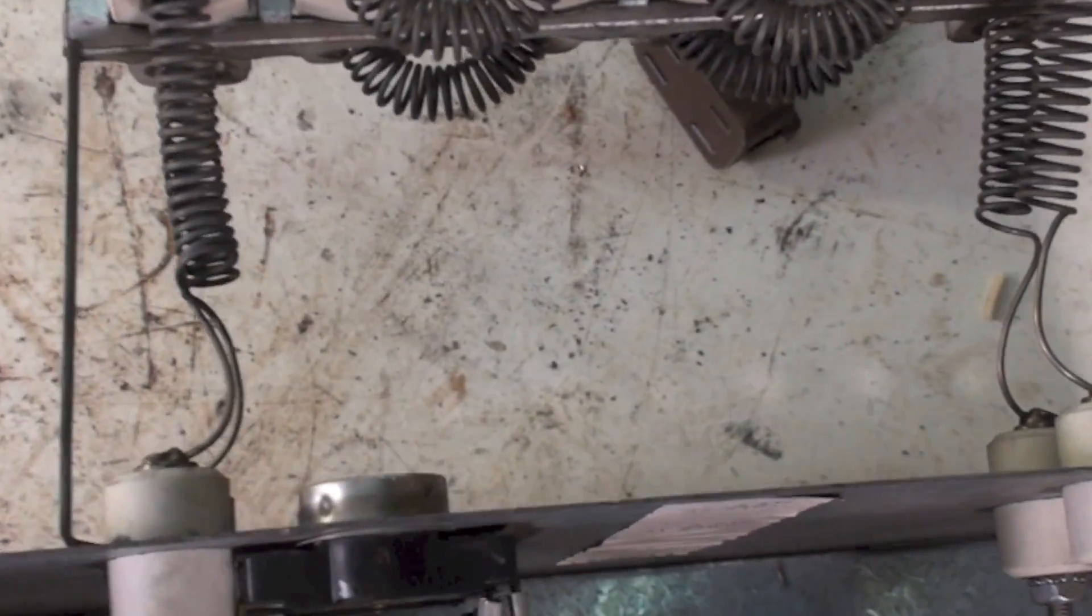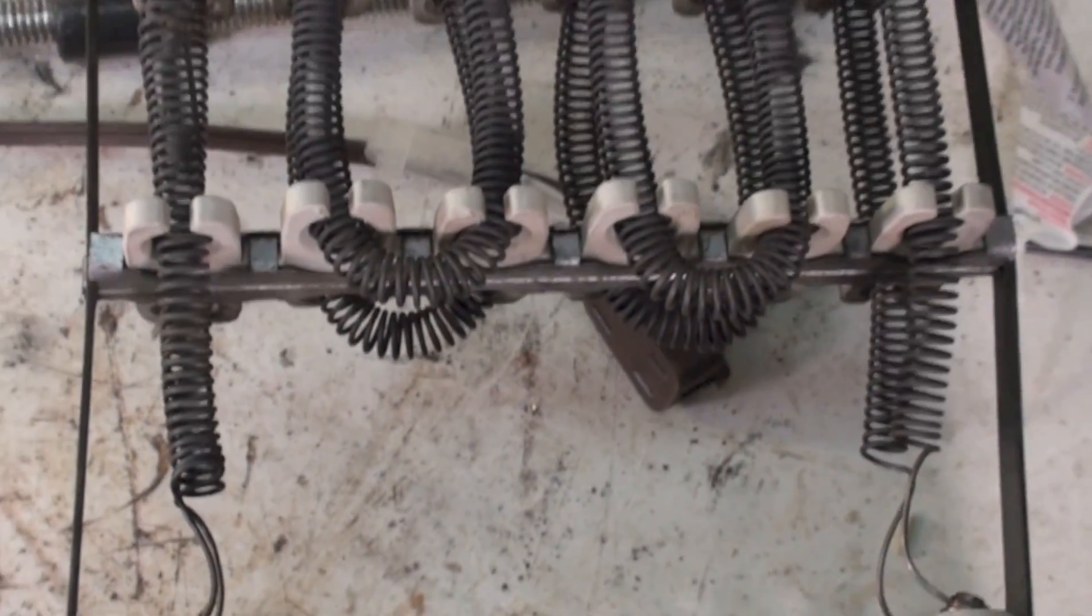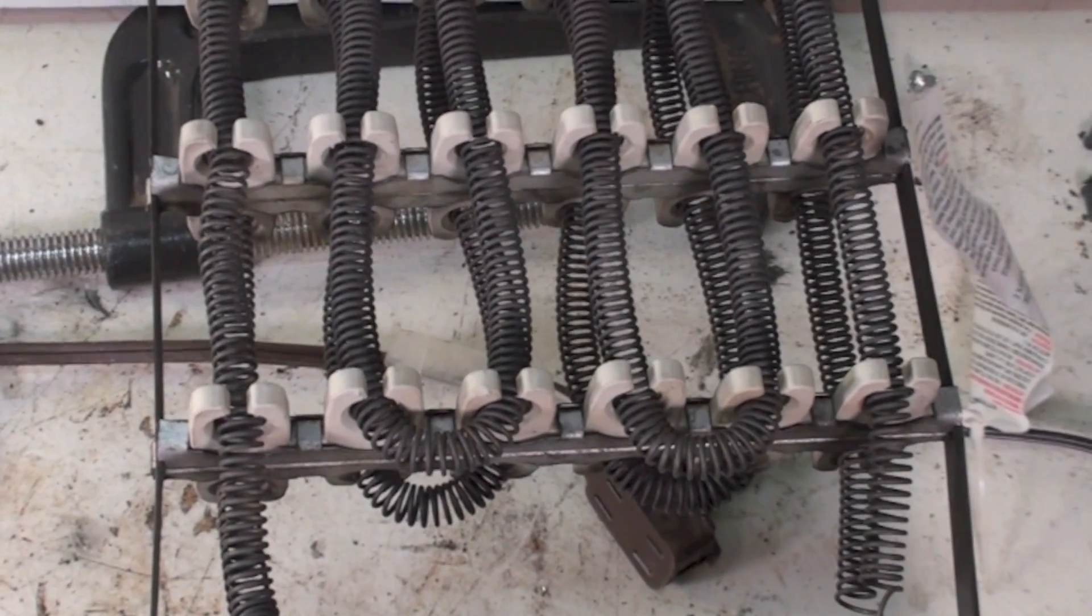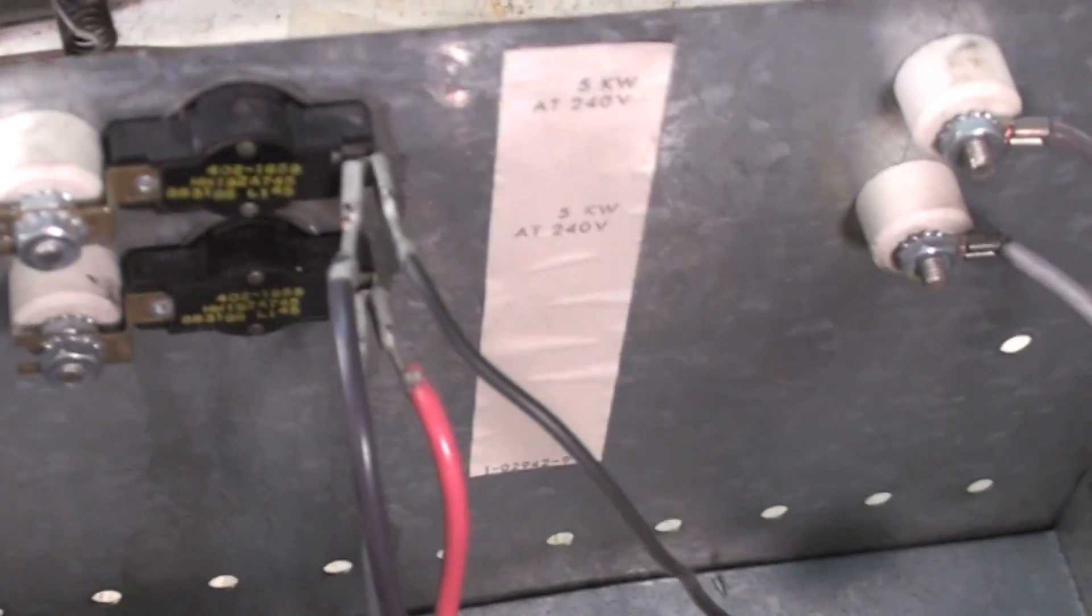But this one doesn't have it, so I guess they just assume the elements are going to burn out. Now they get pretty hot before they burn out, but that's the limit switches on the electric furnaces.